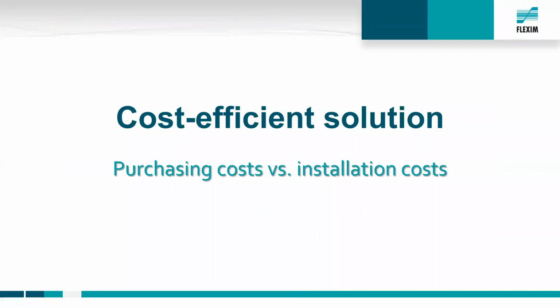So why a cost-efficient solution? It may be that some of you have already had contact with inline meters, mag meters, as well as non-invasive flow measurement solutions like ultrasonic clamp-on meters. And some of you might say the clamp-on meter is usually not the cheapest on the market. This depends on the view. First of all, I would partially agree with this statement and say that on water applications, especially on small pipelines, a mag meter might be more competitive when it comes to purchasing costs. So, we are talking here about purchasing costs.